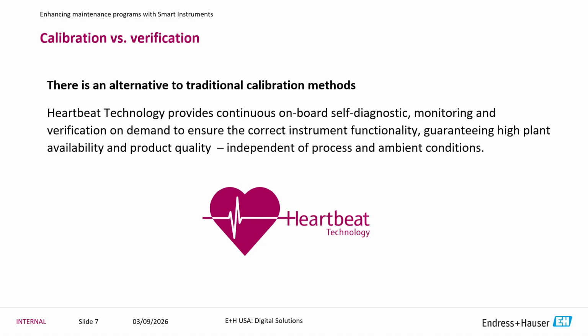Ours at Endress+Hauser is called Heartbeat technology. It's a verification—actually doing inline diagnostics of the entire meter. So it's doing a lot more than just a black box comparison of measurement values. This happens inline during the process, with no process interruption. It's happening behind the scenes. It's still measuring—nothing's changing on your measurement point. But it's doing this continuously.